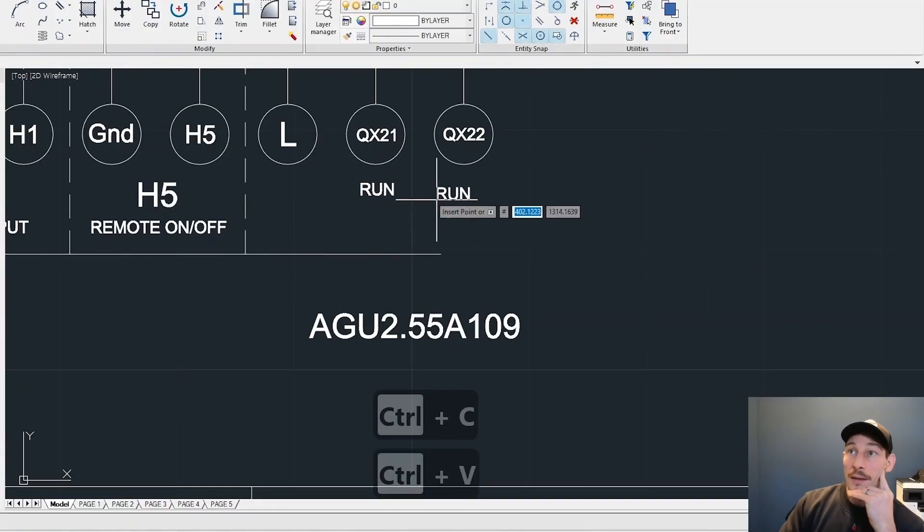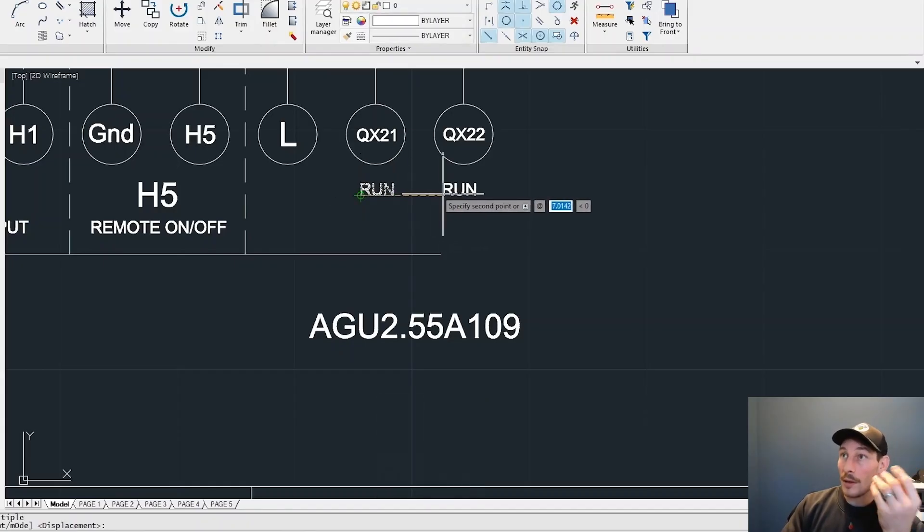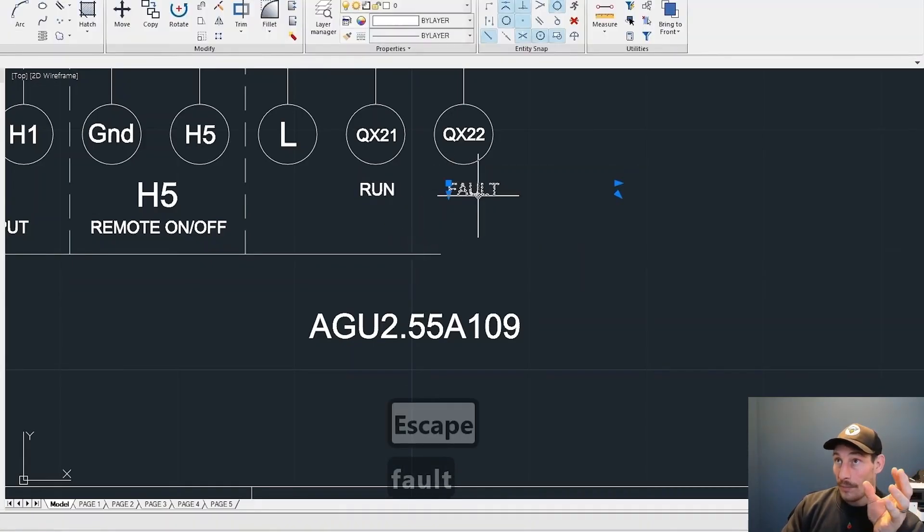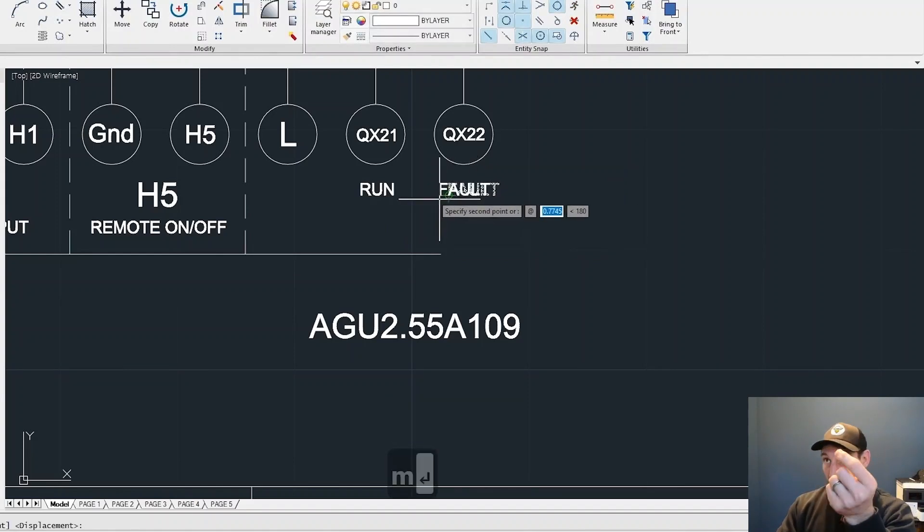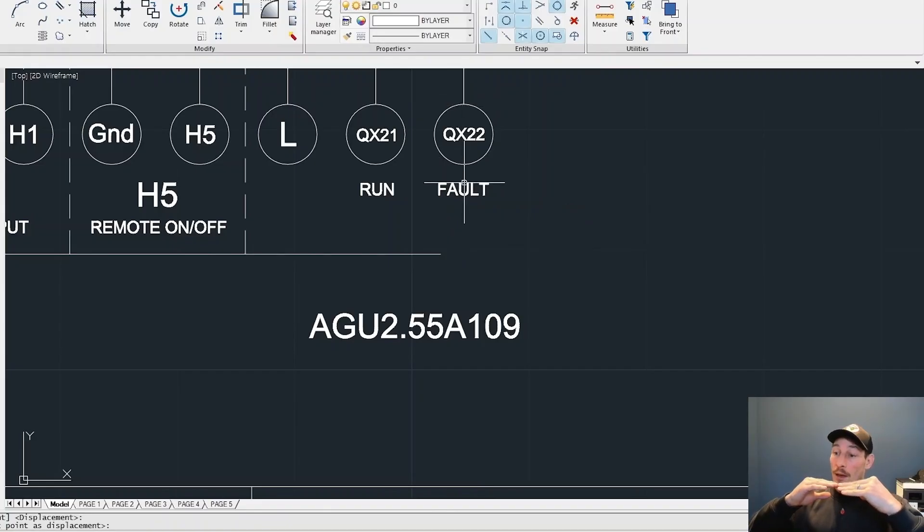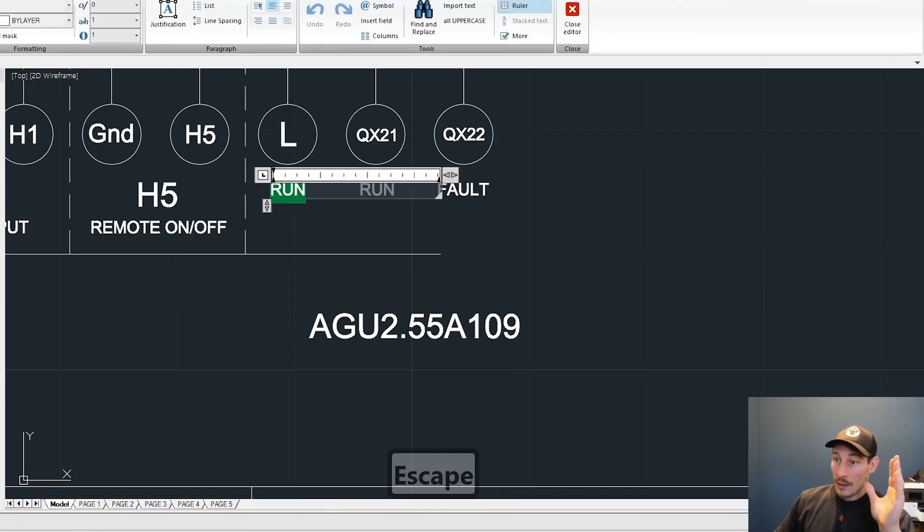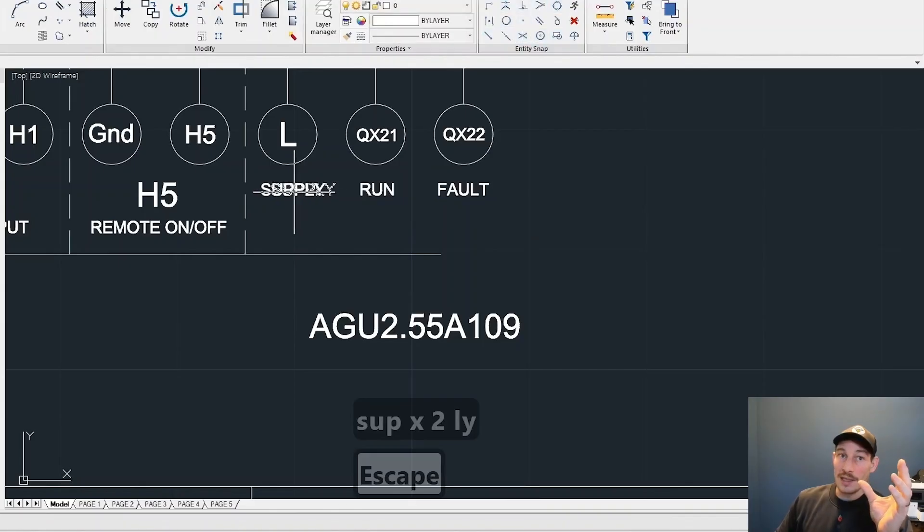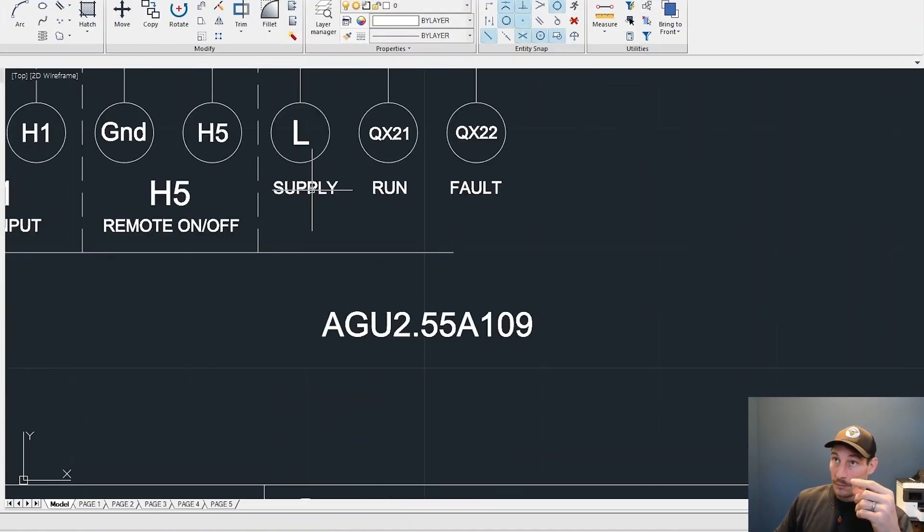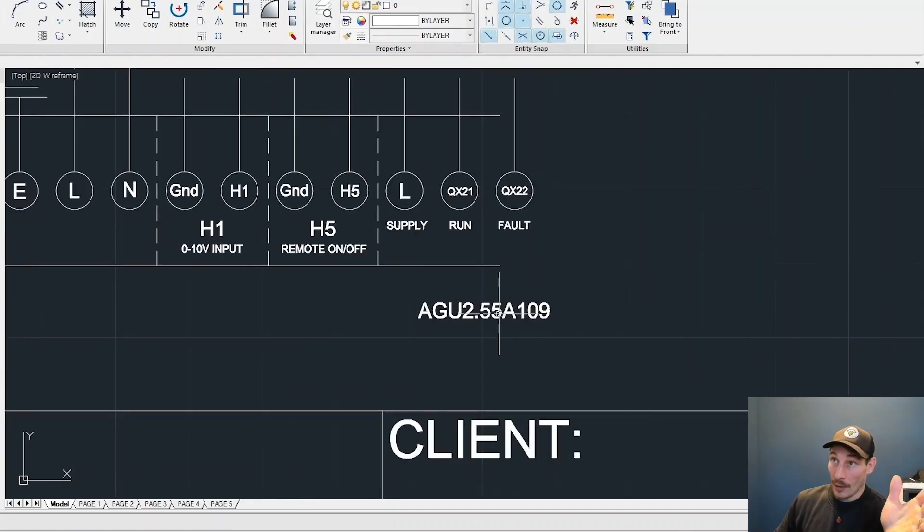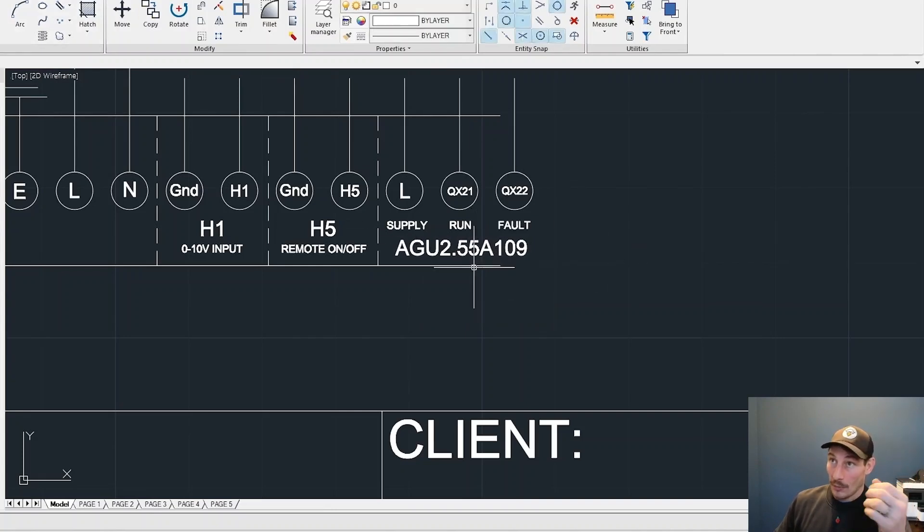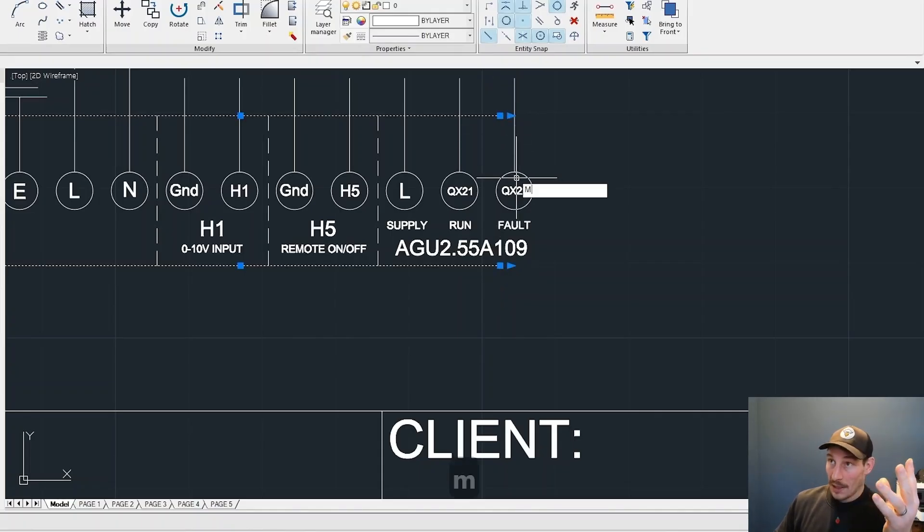This is the run light or the run output and the fault output. If the boiler is running, then it sends a signal back to the control panel. So we're going from the boiler back into the control panel to tell us or to tell the system that it's either running or it's in fault. That's where we see lights flash up on the front of the control panel telling us the state of that boiler so we can quickly identify if there's an issue.